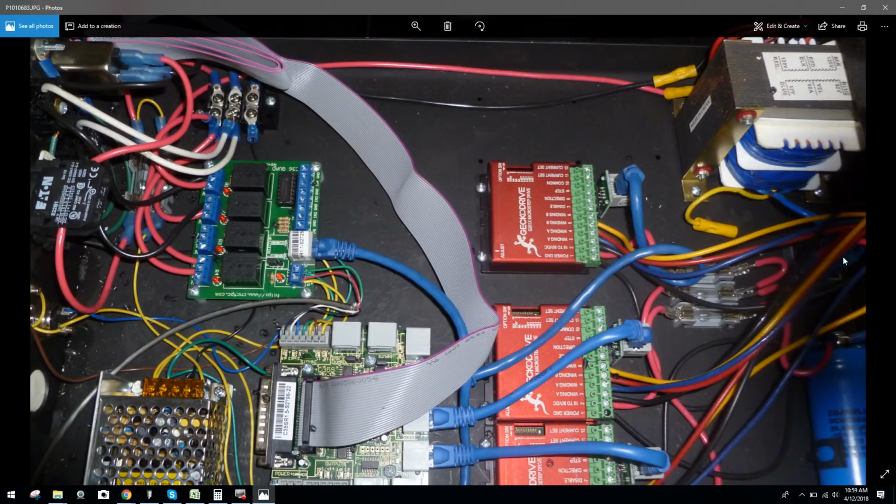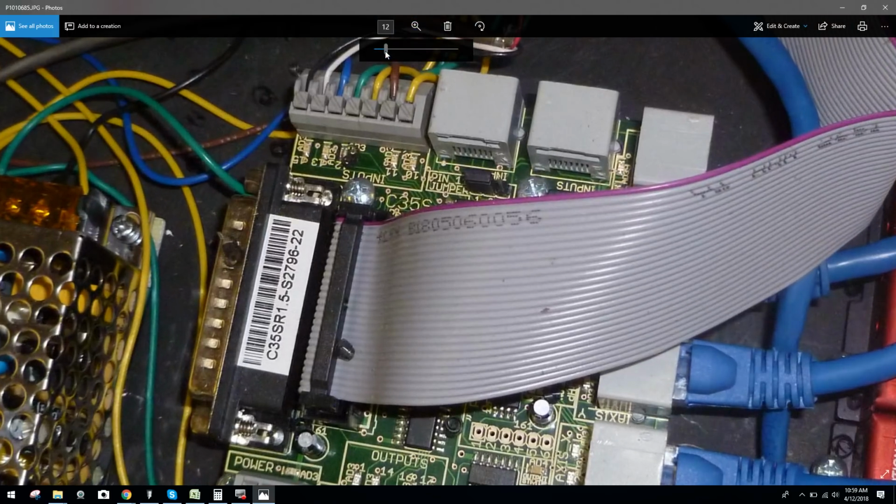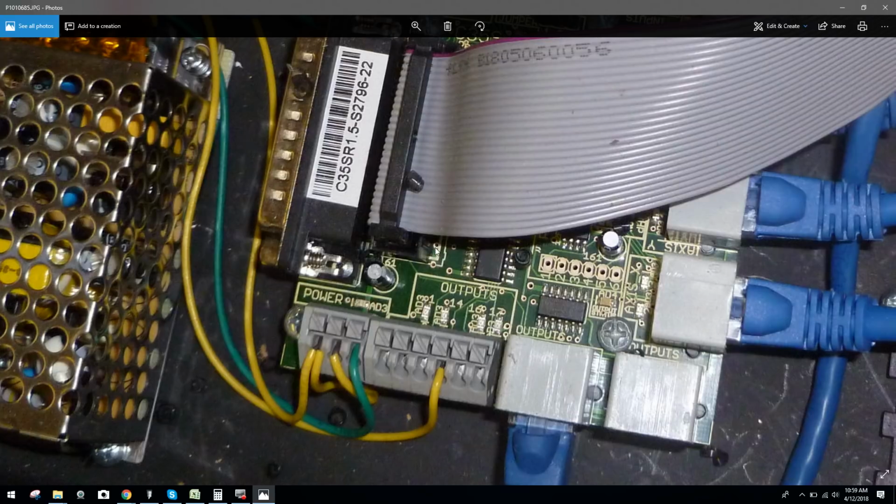If we now actually look at the drives, we're going to come over here. Let's go to the next picture. This isn't showing too much. Well, actually, yeah, it is. If we come down here again, this is just amplifying what we've already discussed. Once again, conductors. Here we go. We've got 2 conductors going into the quick connect terminal block. Wrong. You've got conductors here that are not fully inserted, showing the actual casing of the wire, not all the way bottomed out. Wrong. Once again, here as well.